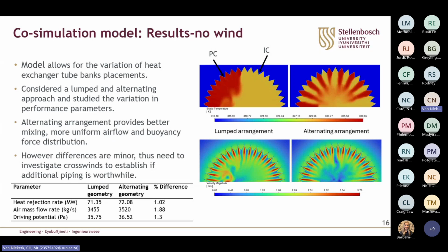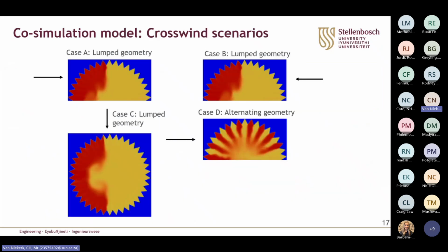So the idea here was to see if it's actually worthwhile to include the alternating arrangement, which will provide better buoyancy force distributions and better airflow mixing within the cooling tower and allow for enhanced performance. But this would then need additional piping to deliver the SCO2 to the different heat exchangers in the practical application. So from our results, we could actually see quite a small difference in performance recovery for the alternating geometry in comparison to the lump geometry. So we had to extend the analysis to crosswind simulations to establish which one of these two arrangements would actually be better to implement into future power plants.